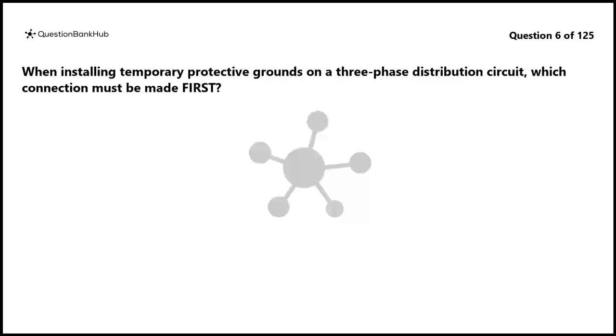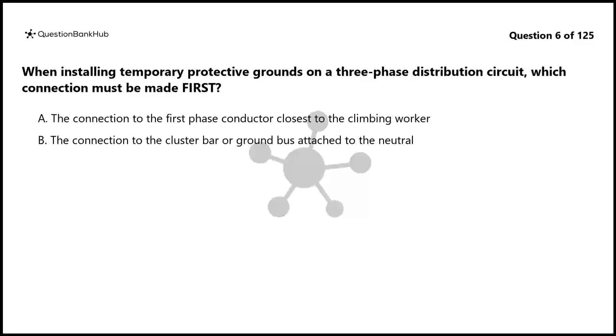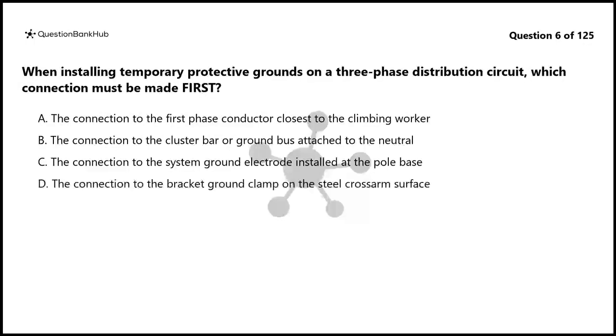Question 6. When installing temporary protective grounds on a three-phase distribution circuit, which connection must be made first? A. The connection to the first phase conductor closest to the climbing worker. B. The connection to the cluster bar or ground bus attached to the neutral. C. The connection to the system ground electrode installed at the pole base. D. The connection to the bracket ground clamp on the steel crossarm surface.